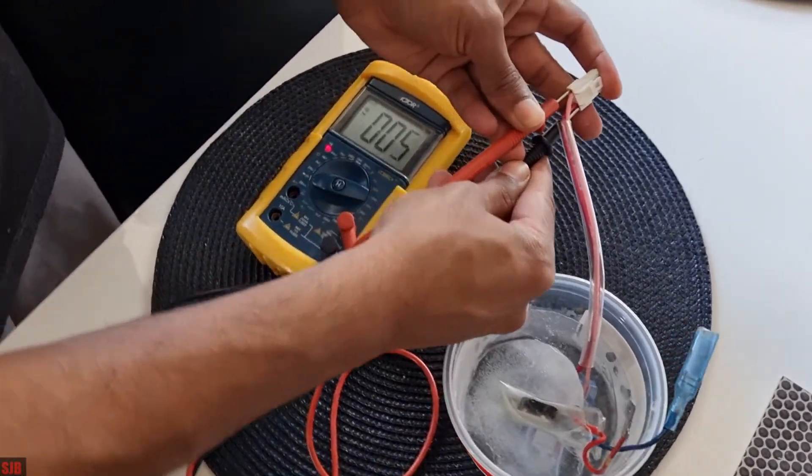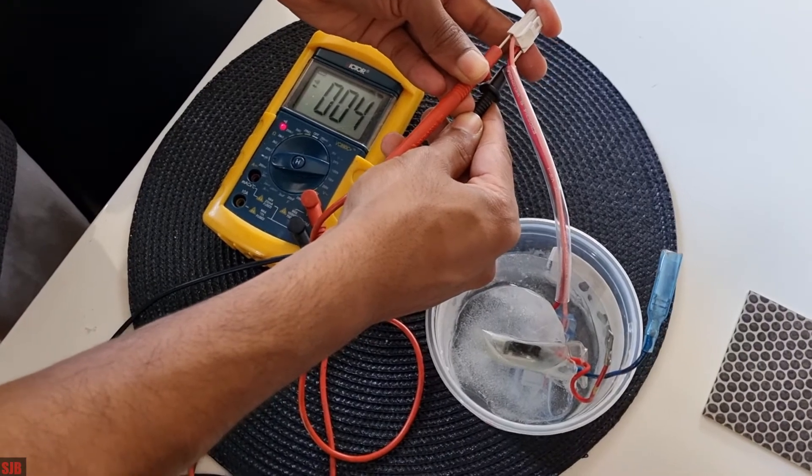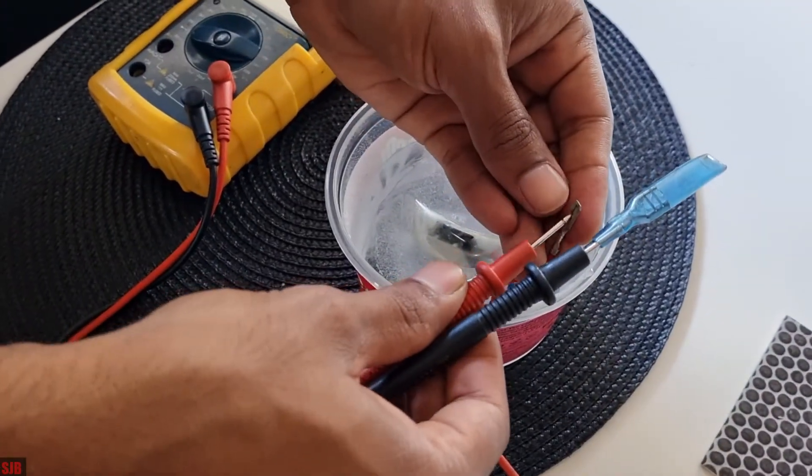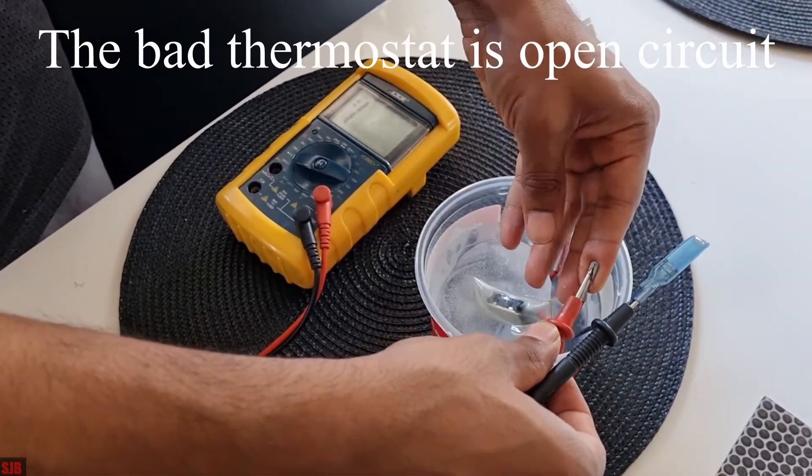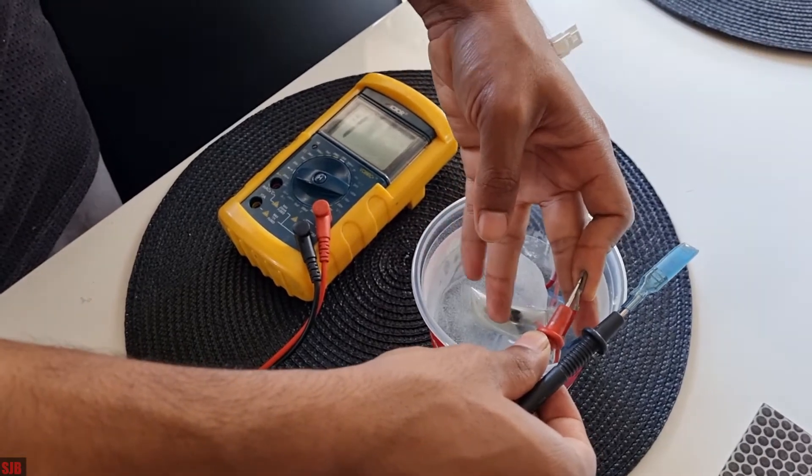As you can see it's showing, and I'll test the old one. Nothing. So that's a bad defrost thermostat just frozen in some water.